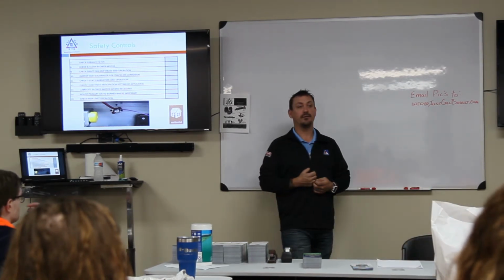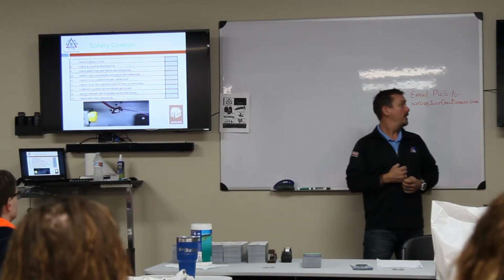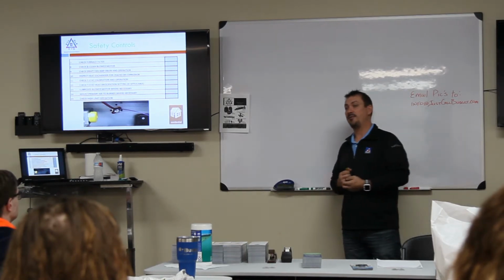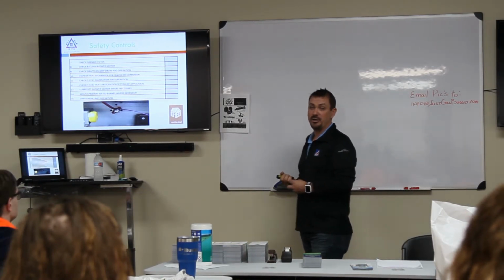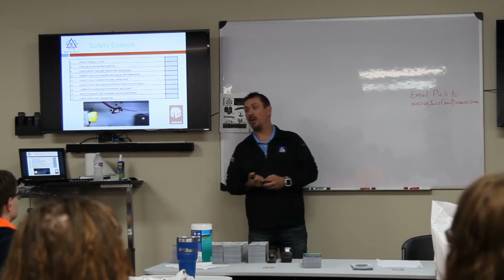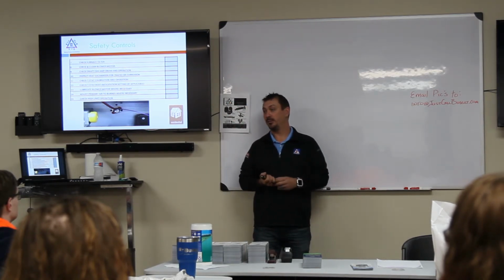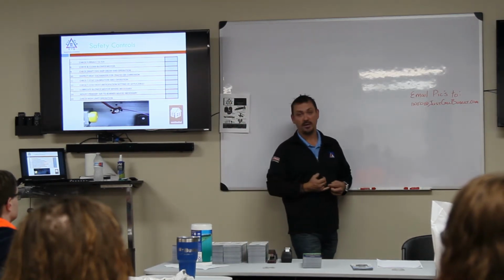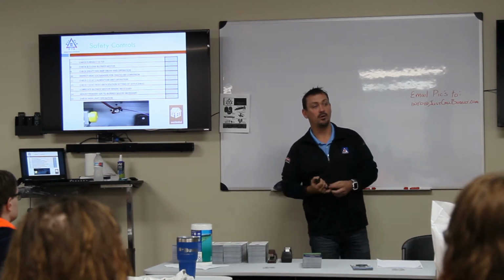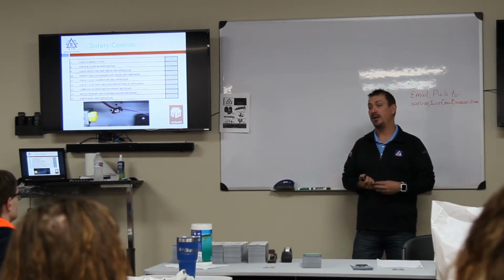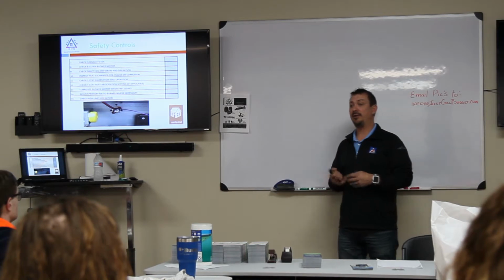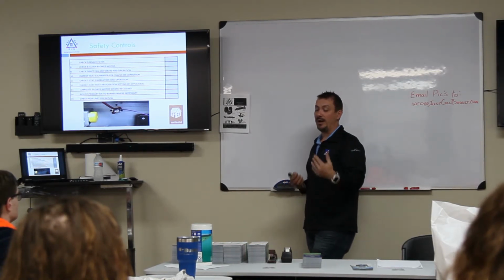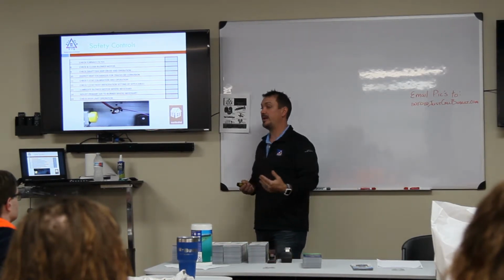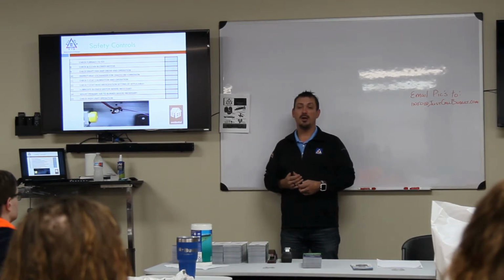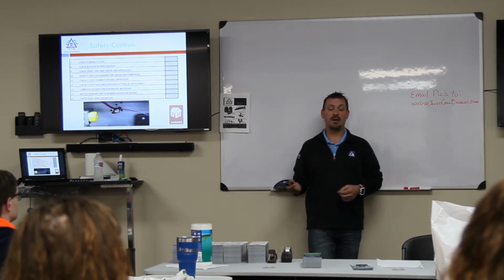go bad. Inspect the heat exchanger for cracks. Now this right here, there's a lot of different ways to check for a crack on your heat exchanger. And the best way is knowledge. The best way to check for a cracked heat exchanger is actually knowing where cracks occur and happen. And every manufacturer and every heat exchanger that's out there has cracks in different places and in different spots. But for the most part, you'll be able to check for a cracked heat exchanger.